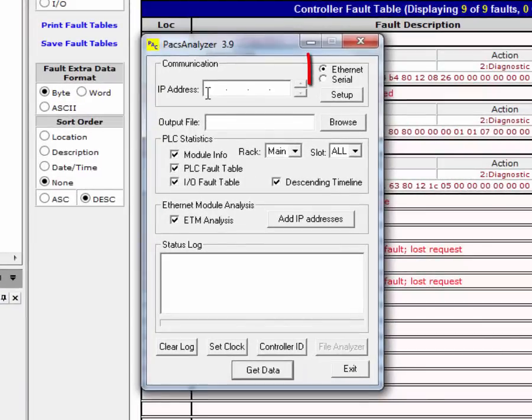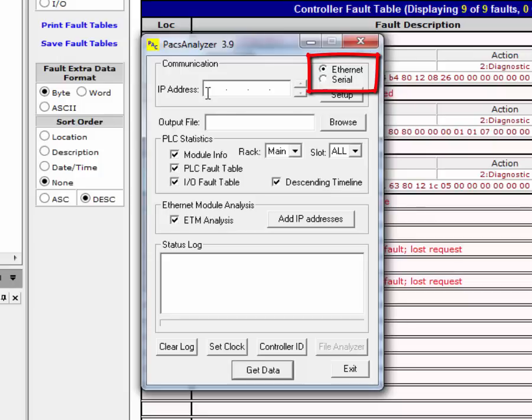The PACS Analyzer tool supports both Ethernet and serial connections. An Ethernet connection is preferred. To use the Analyzer, you must connect to the specific Ethernet module's network. If you connect serially, only module information and fault tables are collected. Ethernet module data is not collected.